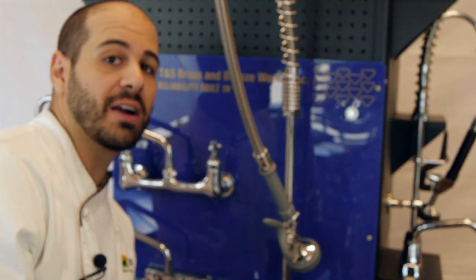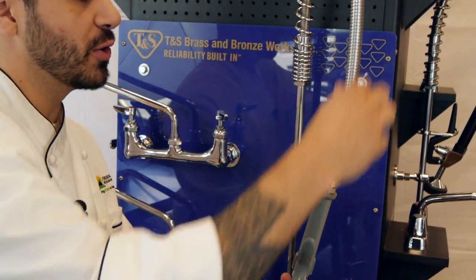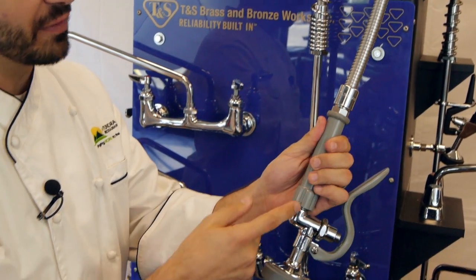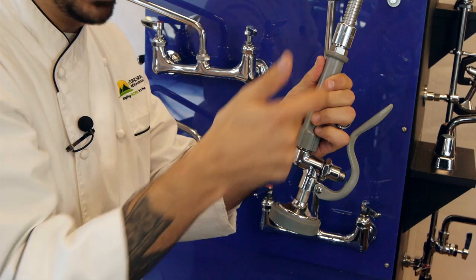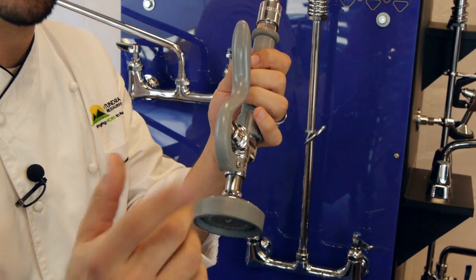The most common areas for leaks on your pre-rinse will typically be in a few common spots: either your hose itself, one of the two washers on either side of your handle, or somewhere around the face plate itself. Here's how we fix those.